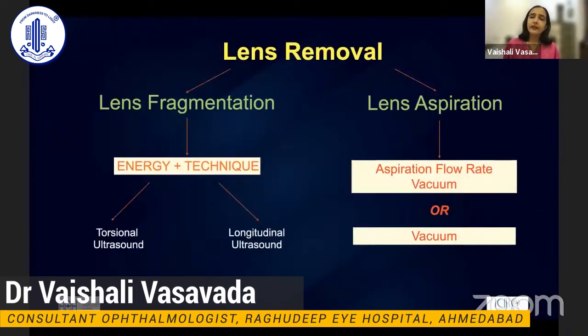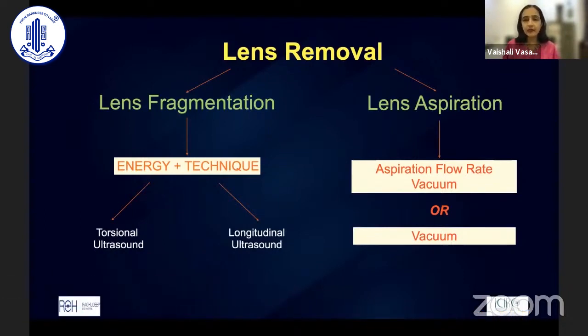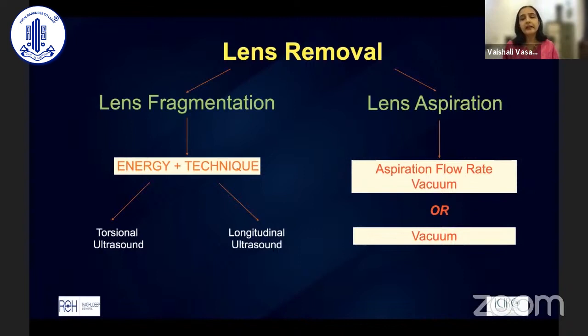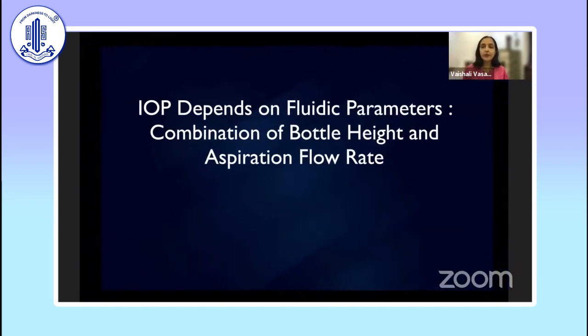When we talk of cataract surgery or phacoemulsification — whether it's FLACS or manual phaco — we are dealing with energy in the form of ultrasonic or femtosecond laser, and how we remove the lens and cortical matter. Whether you use a Venturi or peristaltic system, it is the flow of fluid that matters. For peristaltic machines, we use a combination of vacuum, aspiration flow rate, and bottle height, and whatever goes in via irrigation pressure must be balanced with whatever comes out.